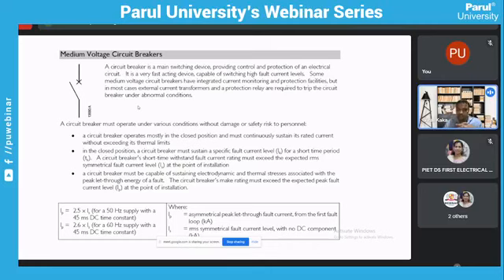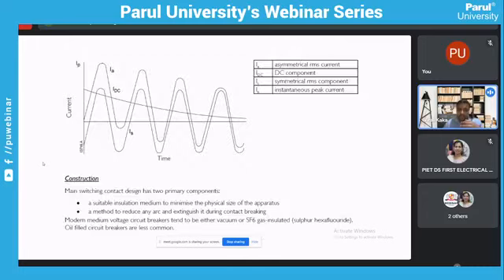So this is just a brief explanation of the medium voltage circuit breaker. The following detail is the IP rating, or IP class, which is the asymmetrical peak let-through fault current capacity from the first loop. Normally it's 2.5 times Ik for 50 hertz and 2.6 times Ik for 60 hertz. This is a waveform of our fault current. As we know, in a fault current waveform we don't normally see only an RMS current. There will also be a bit of DC component in our fault current, which has a slow decay, and that's what makes it an asymmetrical RMS current.